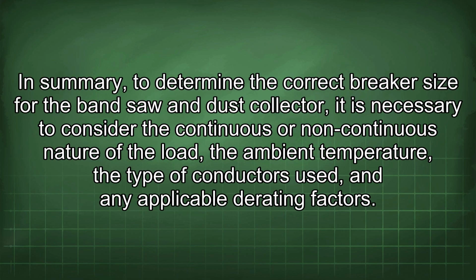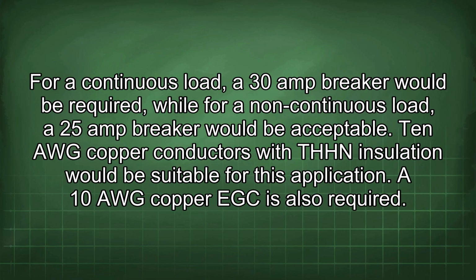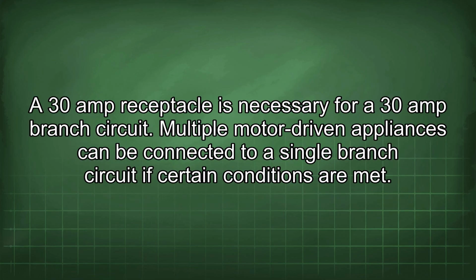In summary, to determine the correct breaker size for the bandsaw and dust collector, it is necessary to consider the continuous or non-continuous nature of the load, the ambient temperature, the type of conductors used, and any applicable derating factors. For a continuous load, a 30 amp breaker would be required, while for a non-continuous load, a 25 amp breaker would be acceptable. 10 AWG copper conductors with THHN insulation would be suitable for this application. A 10 AWG copper EGC is also required. A 30 amp receptacle is necessary for a 30 amp branch circuit. Multiple motor-driven appliances can be connected to a single branch circuit if certain conditions are met.